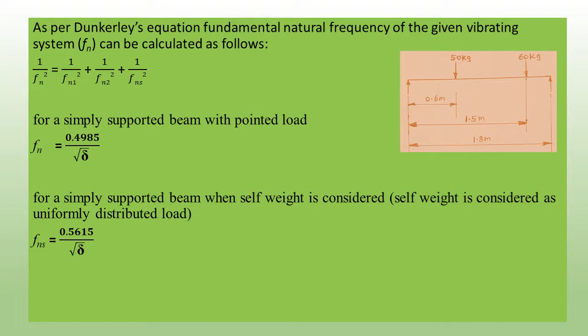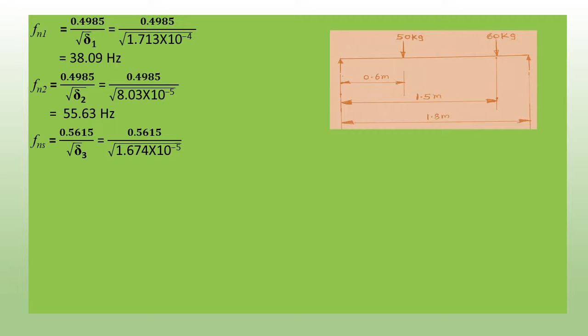Fn1 equals 0.4985 divided by root over delta 1. By substituting the value of delta 1 in the equation, Fn1 equals 38.09 Hz. Fn2 equals 0.4985 divided by root over delta 2. By substituting the value of delta 2, Fn2 equals 55.63 Hz. Fns equals 0.5615 divided by root over delta 3. By substituting the value of delta 3, Fns equals 137.23 Hz.